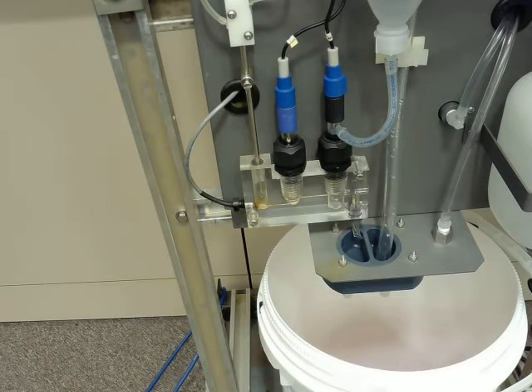So that's the main reason for this buffering, is to raise the pH, get rid of any interference from our H+ that might exist. And if you were to check the pH of the sample coming out of that flow cell, we'd be looking for about an 11. Once we get up to that point, we've kind of negated any interference from the H+, and we should be able to get a good sodium reading.